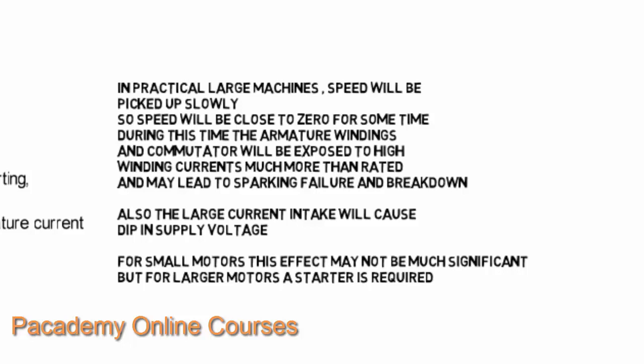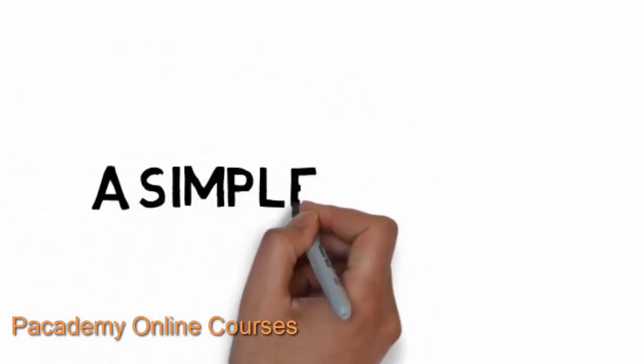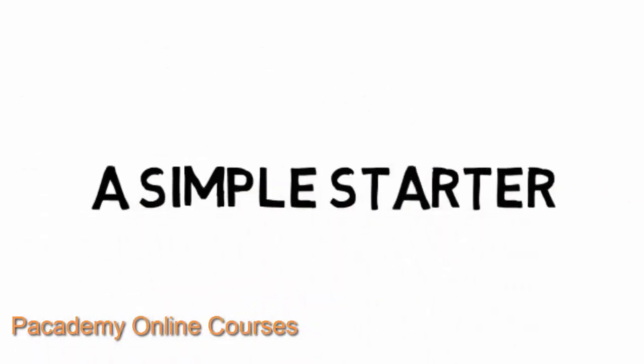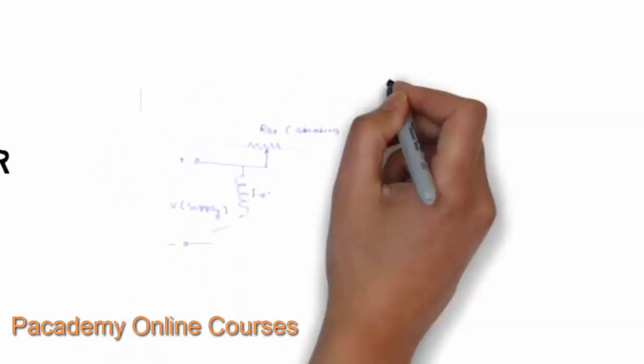The large current intake will also cause a dip in the supply voltage, which may affect the operation of nearby equipment. For small motors the effect of starting may not be significant and may not require any additional equipment, but for large machines it is necessary to reduce the armature current at the instant of starting. This is done by using starters known as DC motor starters. We will now look into the principle of a simple starter.